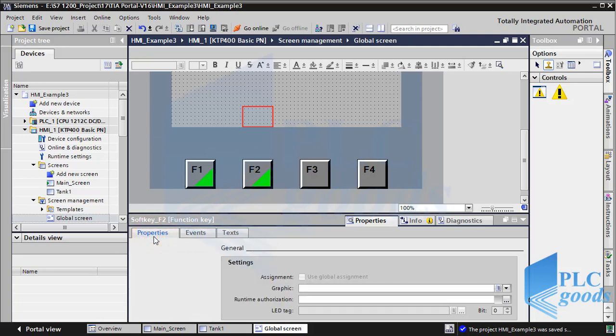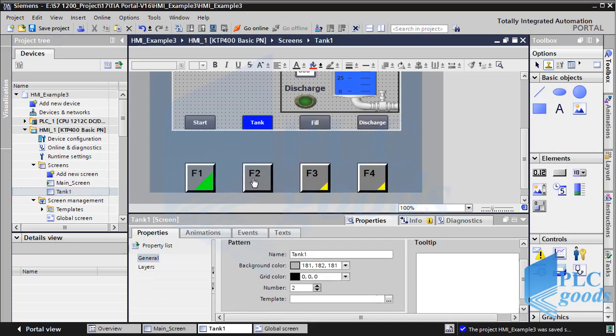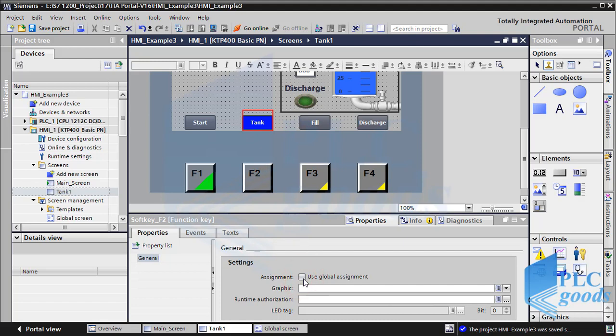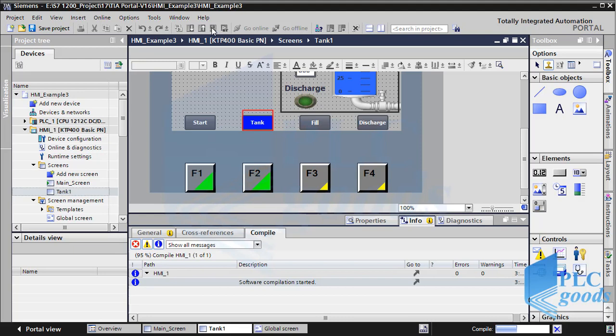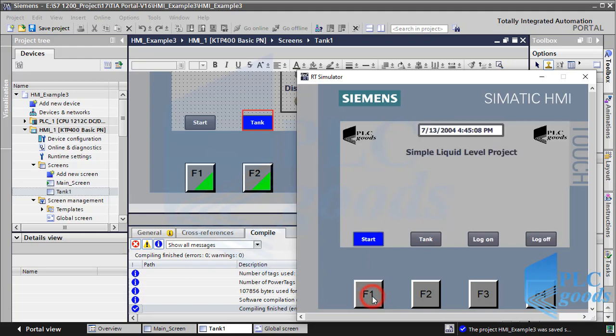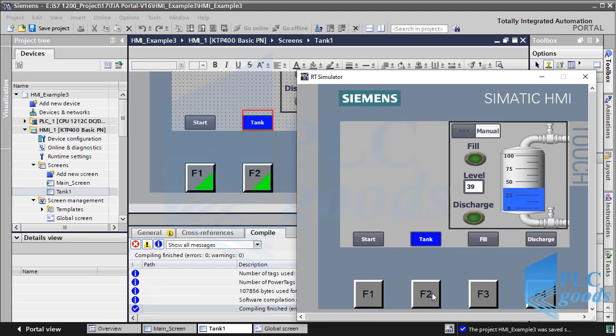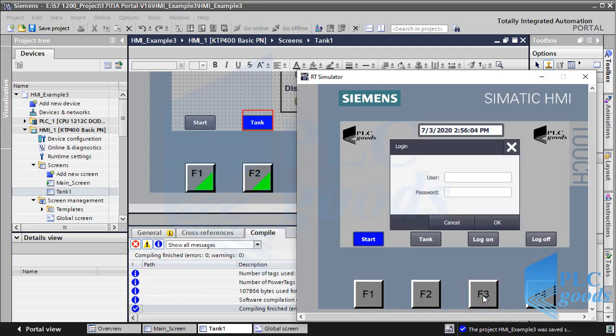Like local assignment, here we can also define and use a graphic for F1 to F4. Let's go back to the tank screen. As you see, F2 doesn't have a green triangle — I forgot to activate its global assignment in this screen. In simulation, we can activate the start and tank screens with F1 and F2, use F3 and F4 for tank filling and draining on the tank screen, or use F3 and F4 to log on and log off in the start screen.